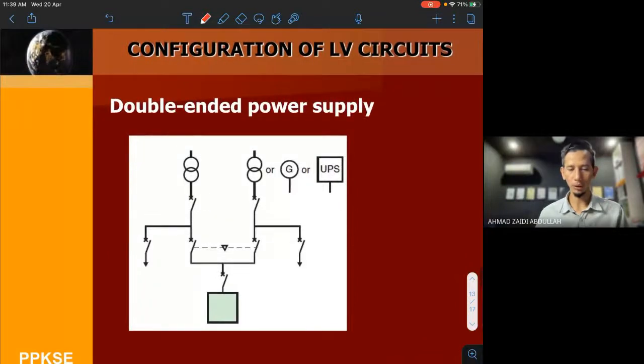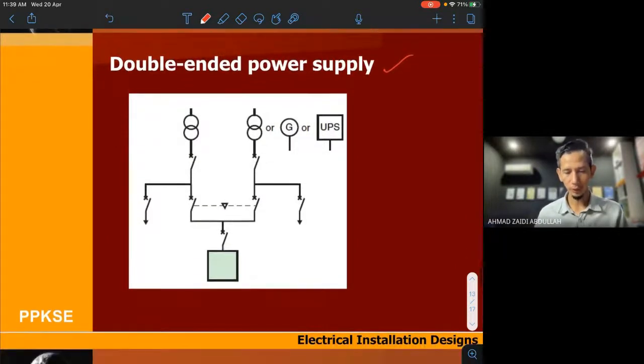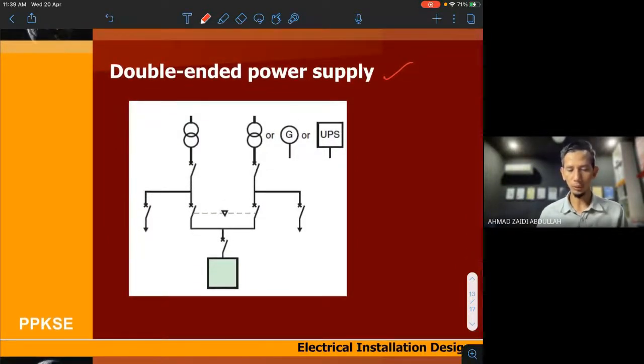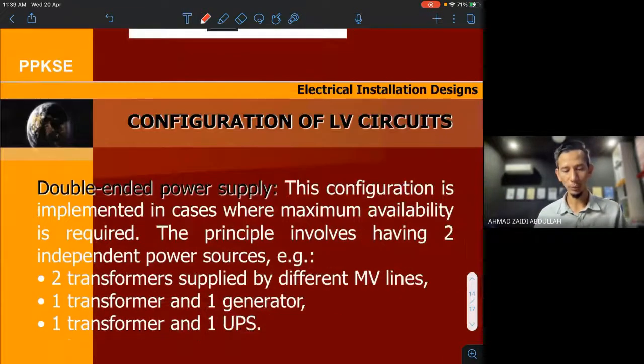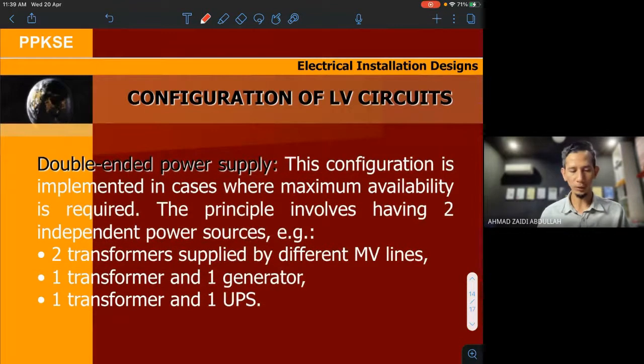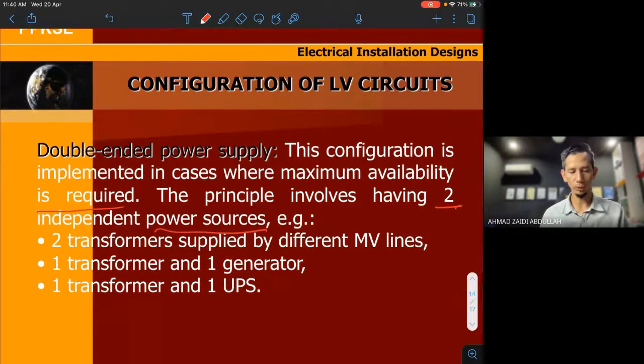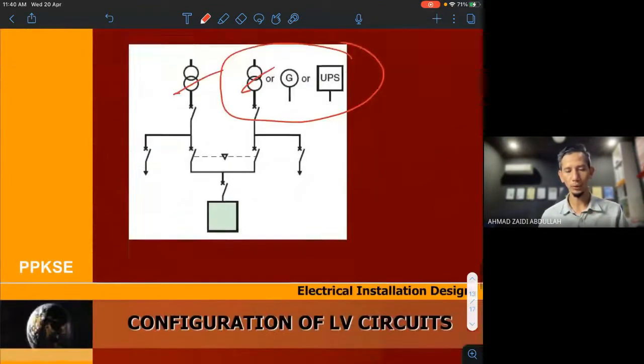And then this is what we call a double-ended power supply. Double-ended means that you can have several types of the output. This configuration is implemented in cases where maximum availability is required. The principle involves two independent power sources. So, okay, two. Either two transformers supplying different MV. We have two transformers, so one or this one.